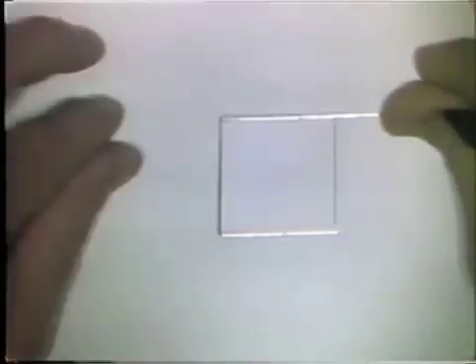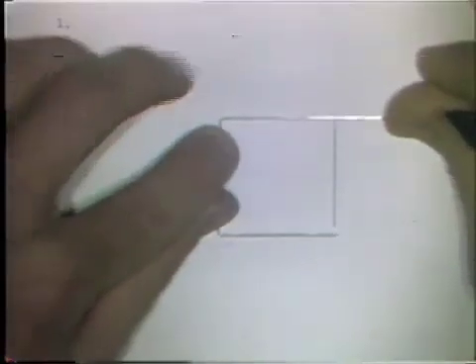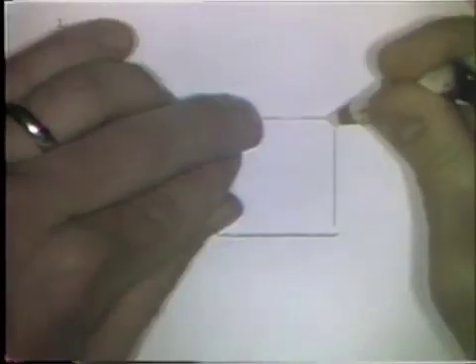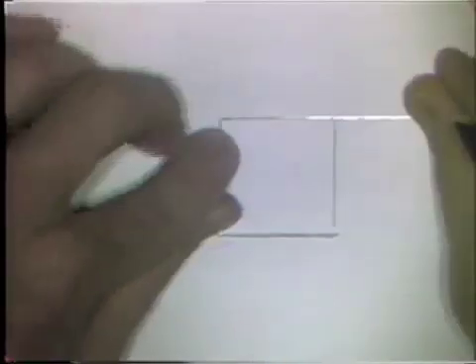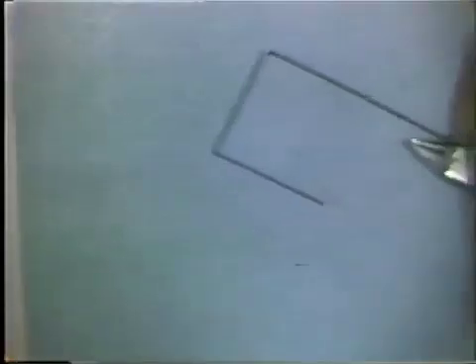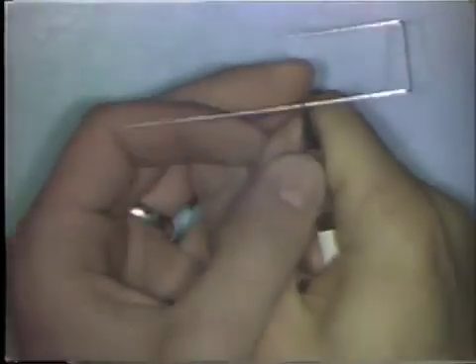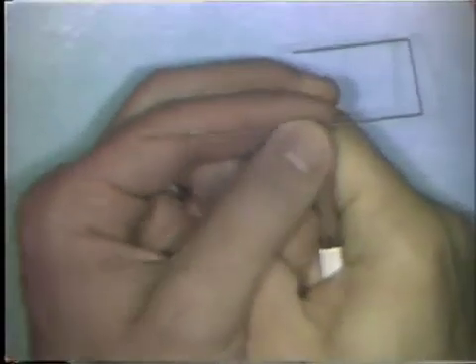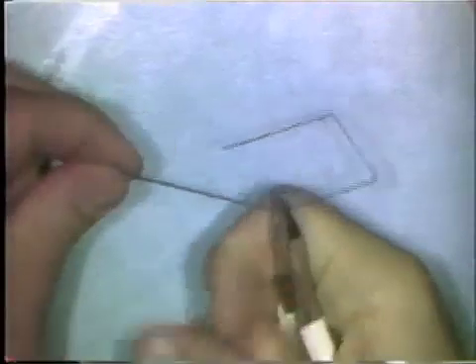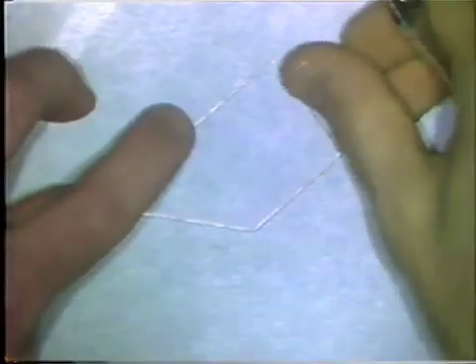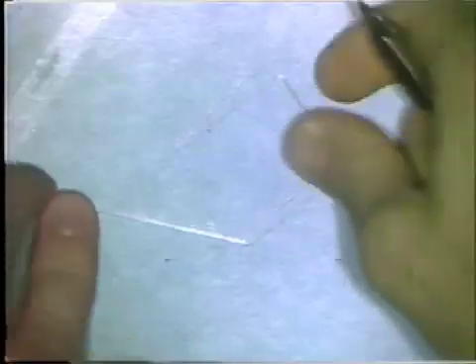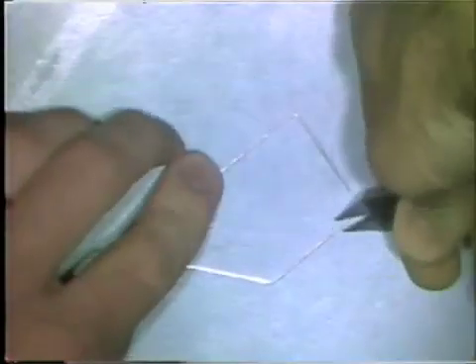Place the wire back on the pattern and in exactly the same manner, mark the wire at the corner where you want the third bend to be made. Complete the bending of this third right angle bend. First, about 30 degrees. Check the flatness, and then complete the final leg.